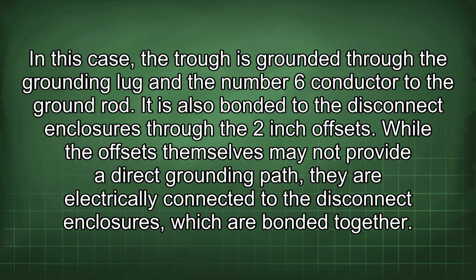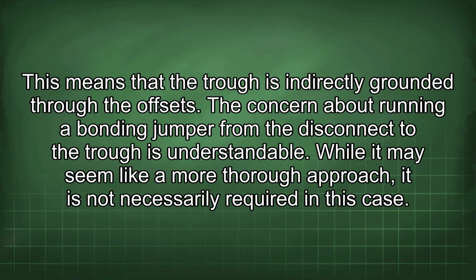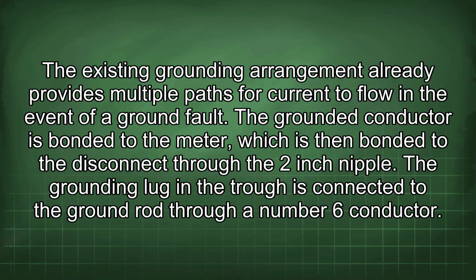While the offsets themselves may not provide a direct grounding path, they are electrically connected to the disconnect enclosures, which are bonded together. This means that the trough is indirectly grounded through the offsets. The concern about running a bonding jumper from the disconnect to the trough is understandable. While it may seem like a more thorough approach, it is not necessarily required in this case. The existing grounding arrangement already provides multiple paths for current to flow in the event of a ground fault. The grounded conductor is bonded to the meter, which is then bonded to the disconnect through the 2-inch nipple.